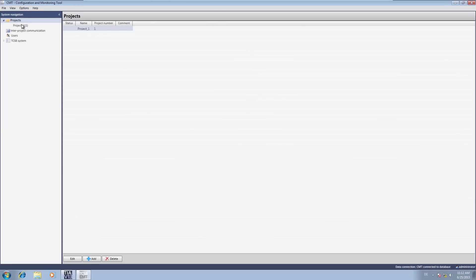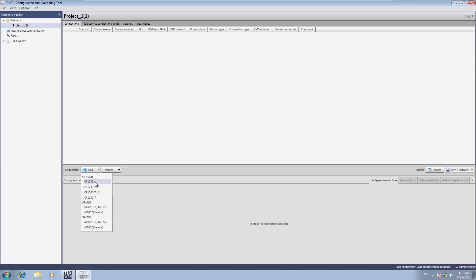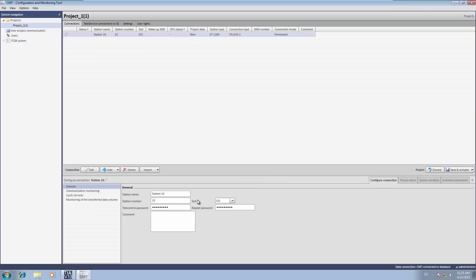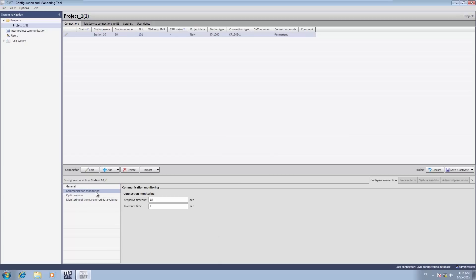For the configuration of the Telecontrol Server BASIC, we now switch to the so-called Configuration and Monitoring Tool, or CMT for short. In the CMT, we create an S7-1200 station with CP1243-1. As with our TIA Portal configuration, this is station number 10 and project number 1. In order for the station to establish an authenticated connection with the Telecontrol Server BASIC, we enter the password already specified in the TIA Portal. Similar to the TIA Portal, we adopt the default parameters for the link monitoring also in the Telecontrol Server BASIC. The configuration of station 10 is now complete and we save and activate the station. This completes the configuration in the CMT and the station can now establish the connection to the Telecontrol Server BASIC.